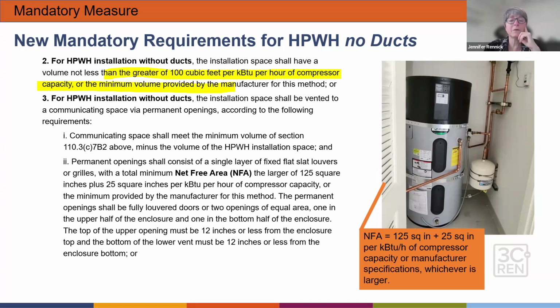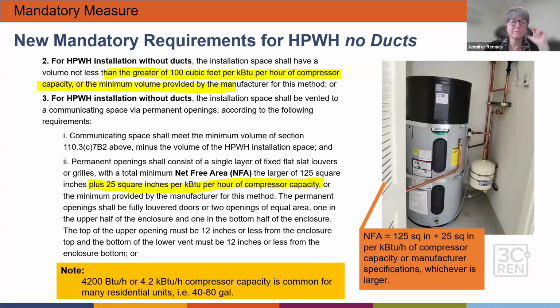Okay, so you might be wondering, what is the kBTU per hour of compressor capacity? I'm going to give you a little thumbnail to remember. And then if you're going to use louvered doors for how this heat pump can communicate with the rest of the house or the rest of the space, to include that as part of this overall volume, there's a formula where you would have 125 square inches plus 25 square inches per kBTU per hour of compressor capacity. So that's the metric again.